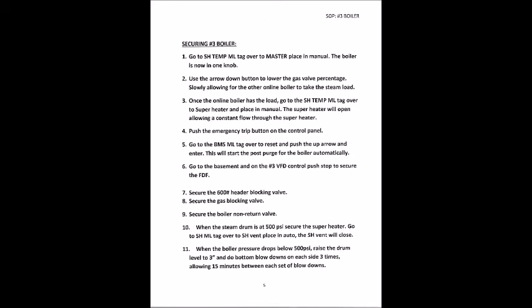4. Push the emergency trip button on the control panel. 5. Go to the BMS ML, tab over to reset and push the up arrow and enter. This will start the post-purge for the boiler automatically. 6. Go to the basement and on the number 3 VFD control, push stop to secure the FDF. 7. Secure the 600 header blocking valve. 8. Secure the gas blocking valve. 9. Secure the boiler non-return valve.